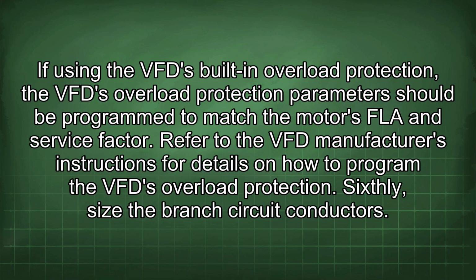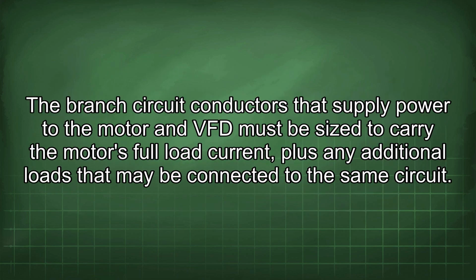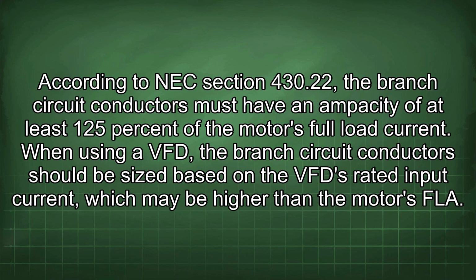Sixthly, size the branch circuit conductors. The branch circuit conductors that supply power to the motor and VFD must be sized to carry the motor's full load current, plus any additional loads that may be connected to the same circuit. According to NEC section 430.22, the branch circuit conductors must have an ampacity of at least 125% of the motor's full load current. When using a VFD, the branch circuit conductors should be sized based on the VFD rated input current, which may be higher than the motor's FLA.